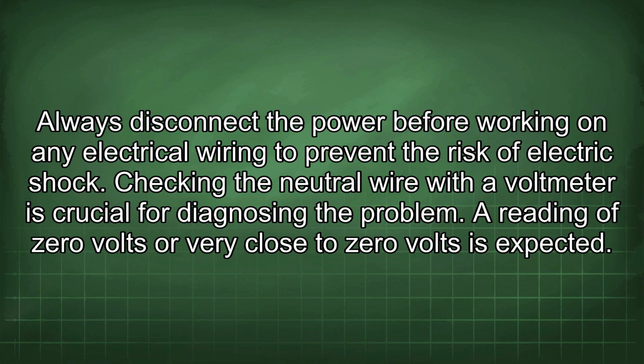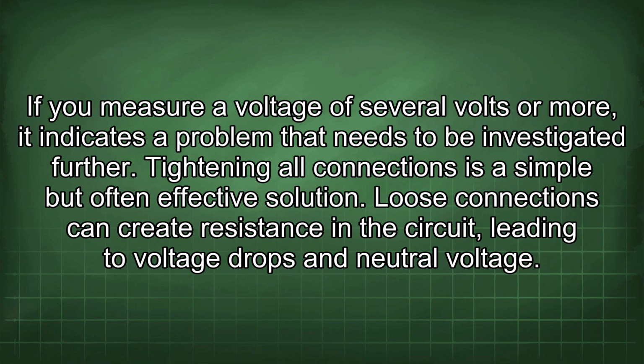Checking the neutral wire with a voltmeter is crucial for diagnosing the problem. A reading of 0 volts or very close to 0 volts is expected. If you measure a voltage of several volts or more, it indicates a problem that needs to be investigated further. Tightening all connections is a simple but often effective solution.